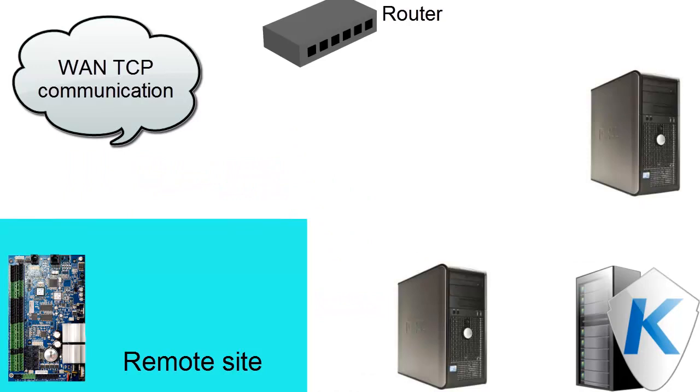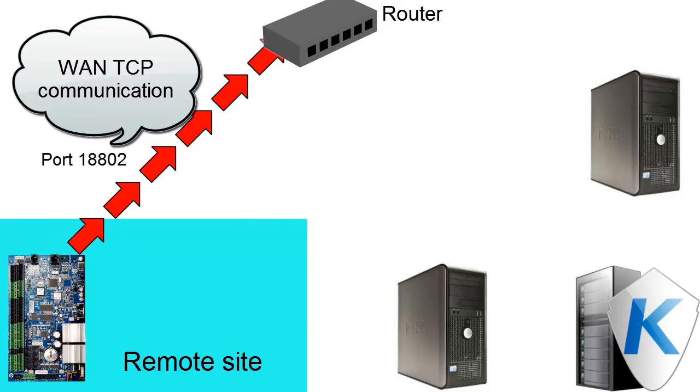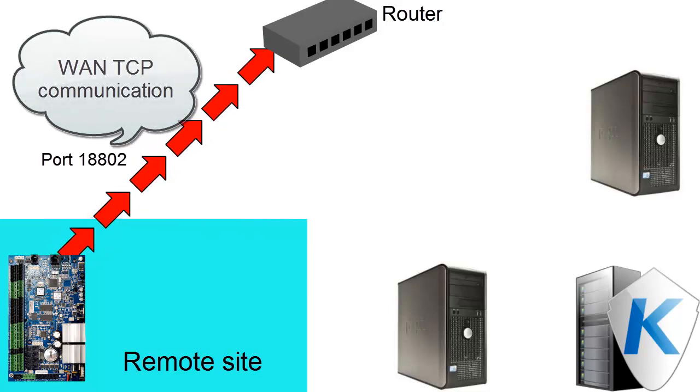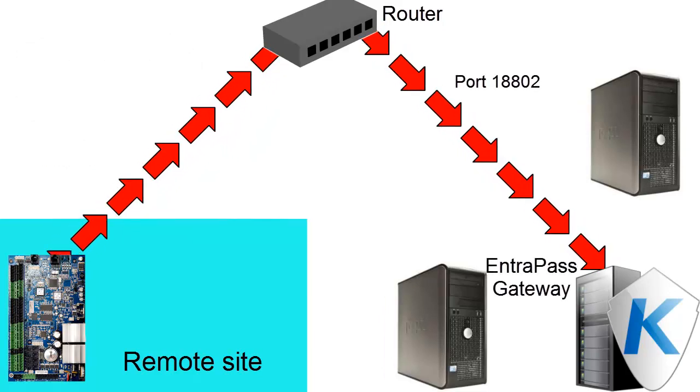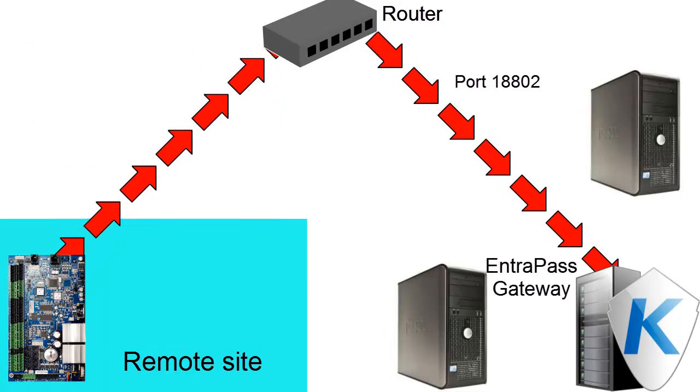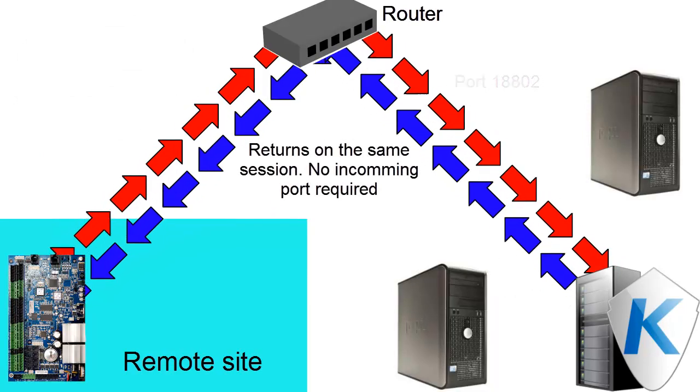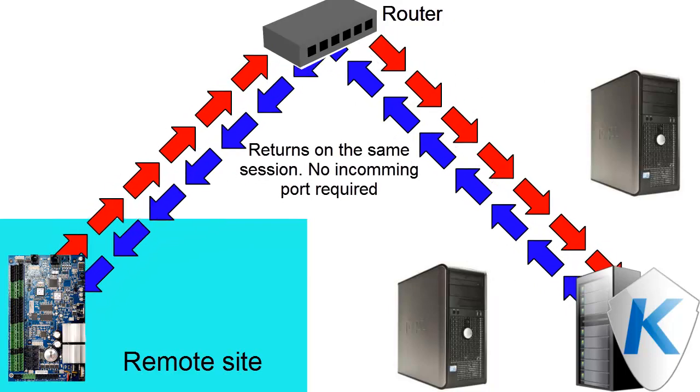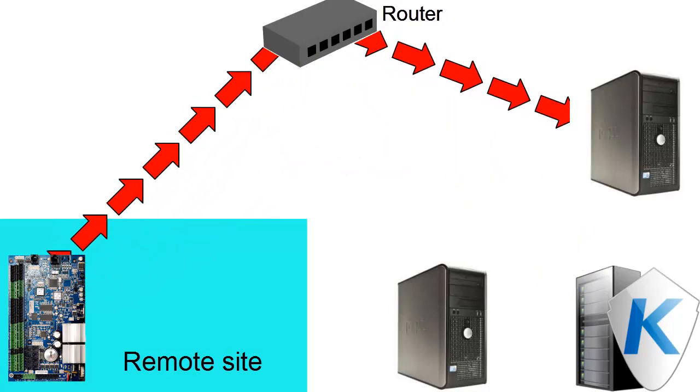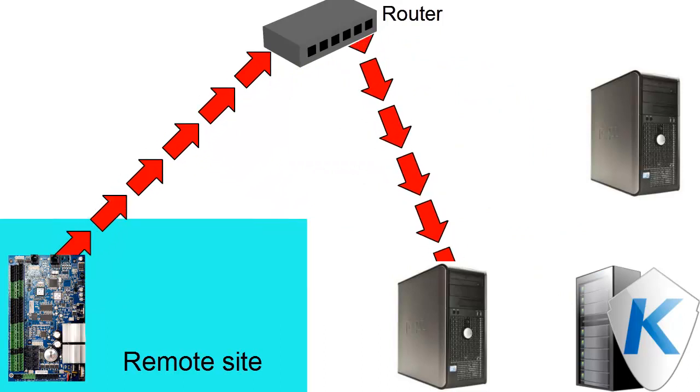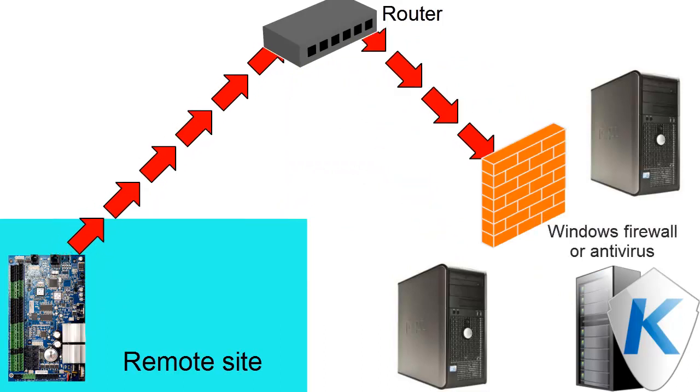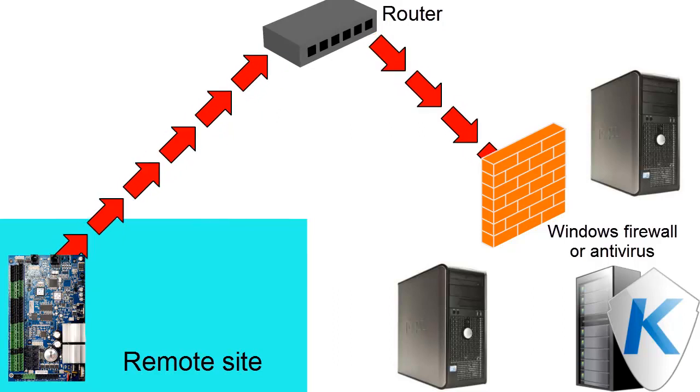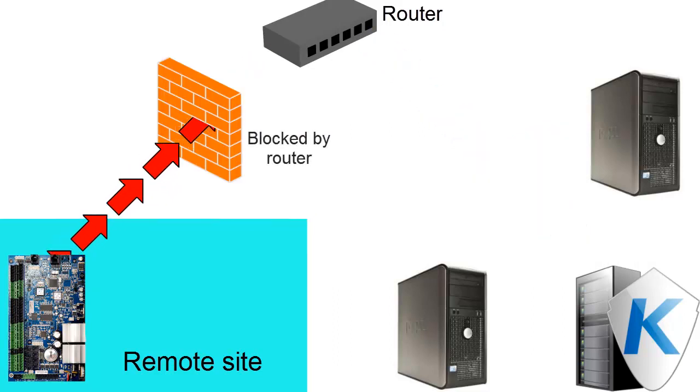Communication through the WAN is slightly different. The controller sends its request on port 18802 to the public IP of where the software is. The port needs to be forwarded to the computer running EntraPass. Request is received by EntraPass. It will answer on a random port. There cannot be any communication if the port isn't forwarded to the correct computer, or if the port is blocked by the computer firewall or antivirus. It can also be blocked by the router.